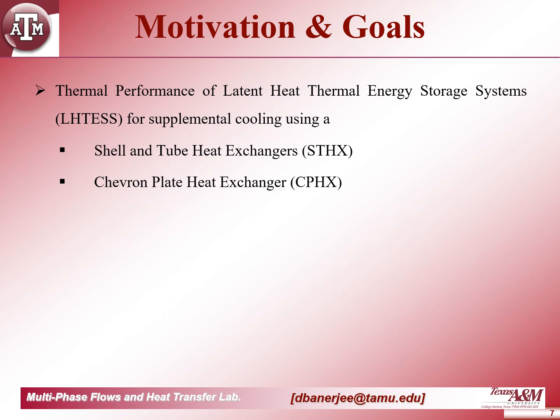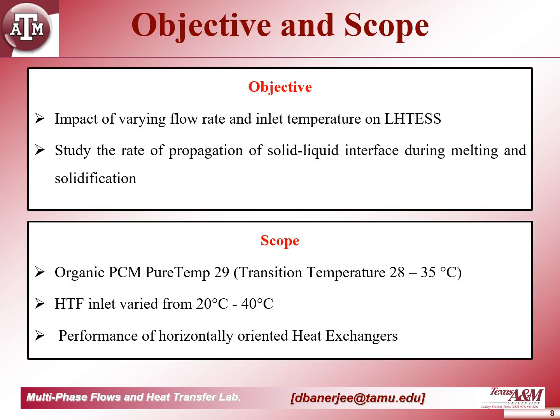Thus, we characterize the thermal performance of a shell and tube heat exchanger and a commercial plate heat exchanger. For this study, organic PCM was used and heat transfer fluid inlet temperature was varied between 20 to 40 degrees Celsius, as it falls in the range of the chosen PCM phase transition temperature. Similarly, flow rate was varied between 3 GPH to 10 GPH.